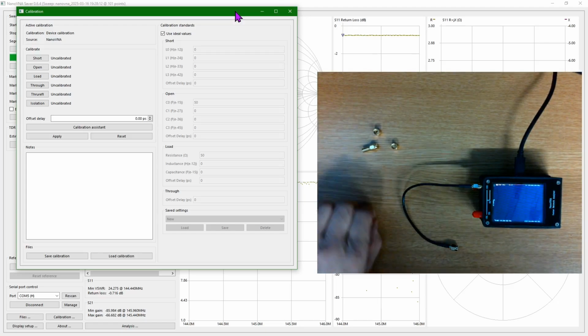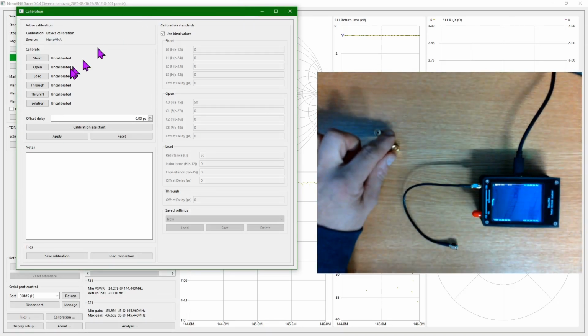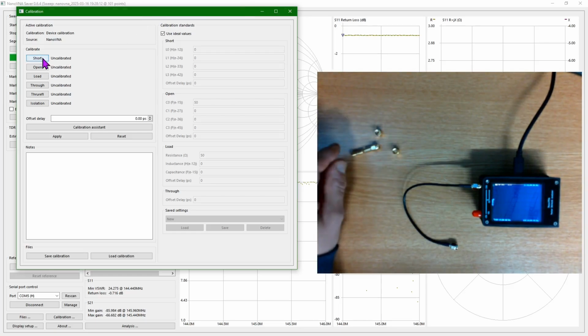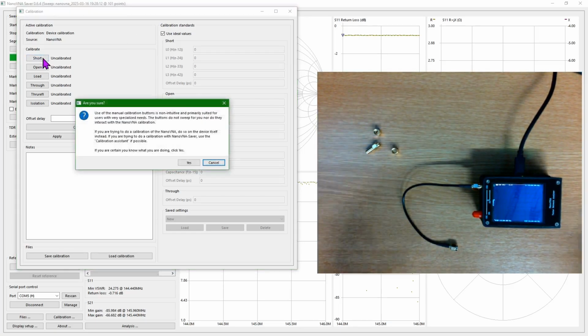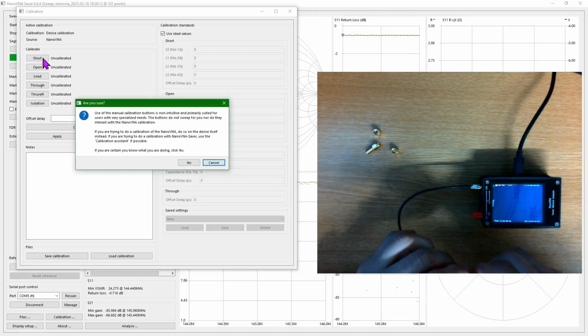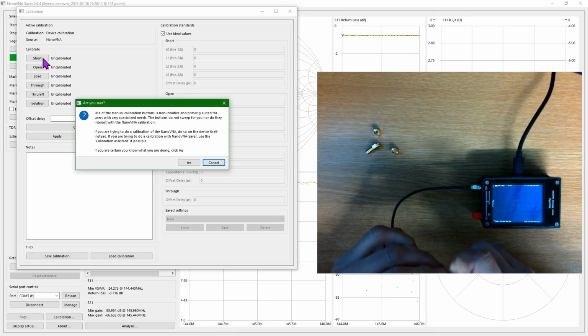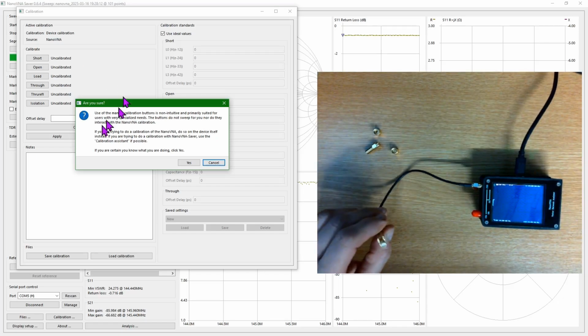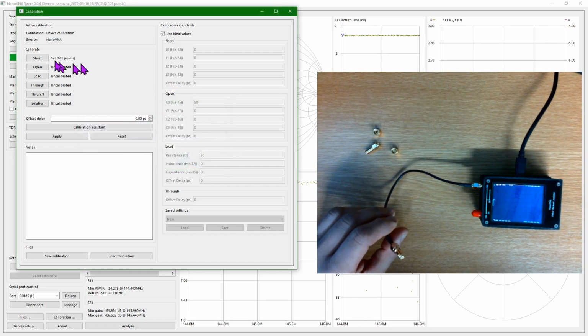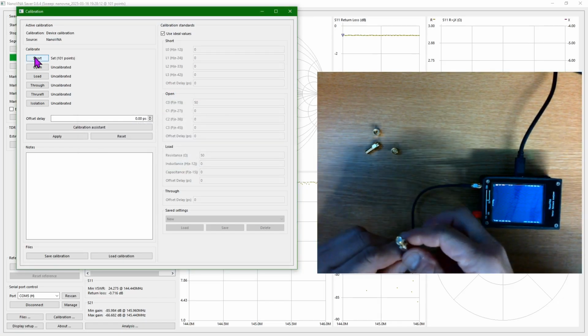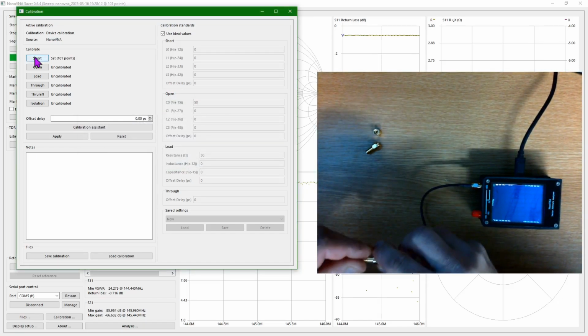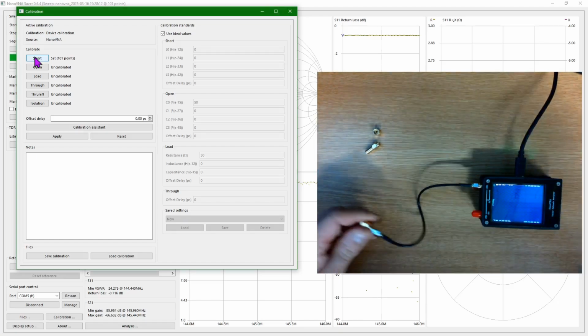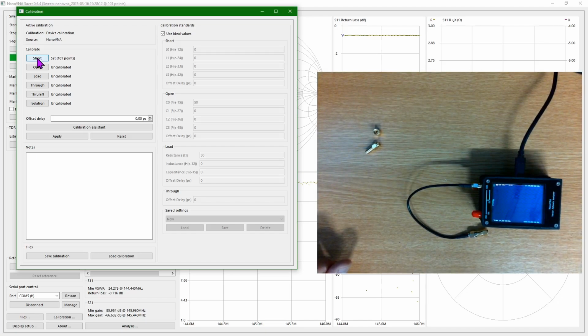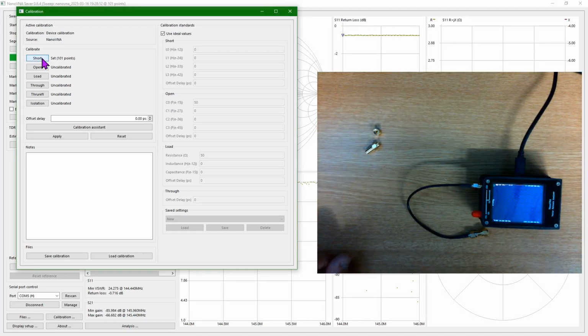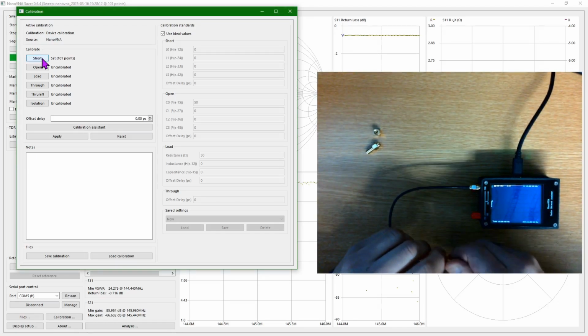So what you do first, if you follow it in order, is quite easy. First of all, you press short to calibrate the short. What this says here is a notice about manual calibration, and it just asks if you're sure you want to do it. So you press yes. Now you've got to have it connected first. So I put the dead short in there and go through and do the short again. Okay, apparently that's done. It does go in the blink of an eye.